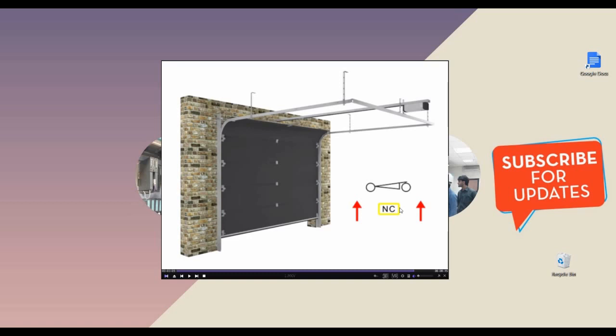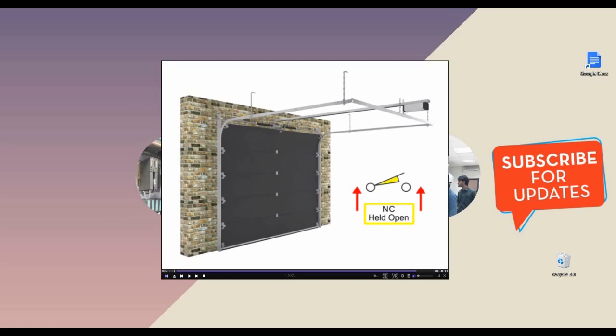When it touches the ground floor, the NC contact will now open — because at the start it was normally closed, we are getting the NC contact. We configure that NC contact so that when it touches the down floor, the limit switch gives an output, putting the NC contact in the open position, which cuts off the supply to the motor.